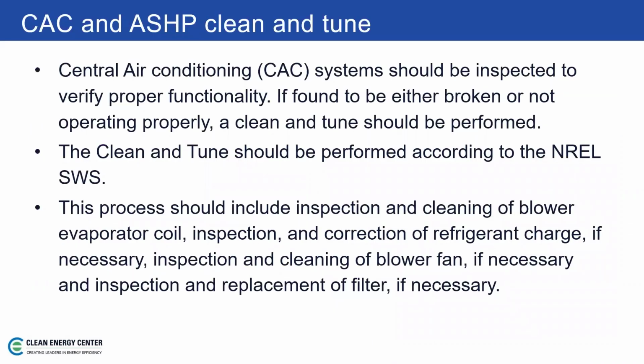Central air conditioning systems should be inspected to verify proper functionality. So this is under the clean and tune part of that. So if found to either be broken or not operating properly, clean and tune should be performed. Again, if it's something that can't be repaired, if you're talking about R22 refrigerant, that's like buying gold on the stock market. So it's not going to be very cost effective to try and repair that system. So think through that, but the clean and tune should be performed according to the NREL SWS.